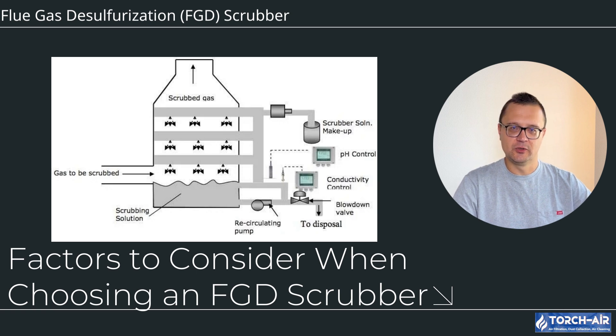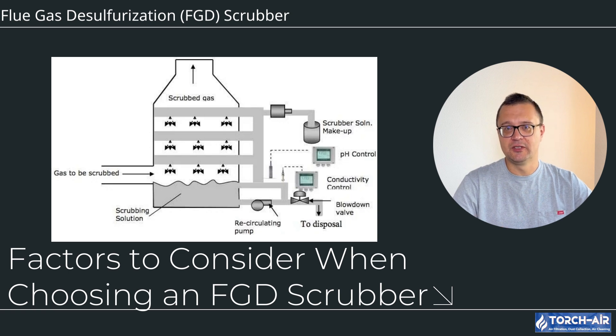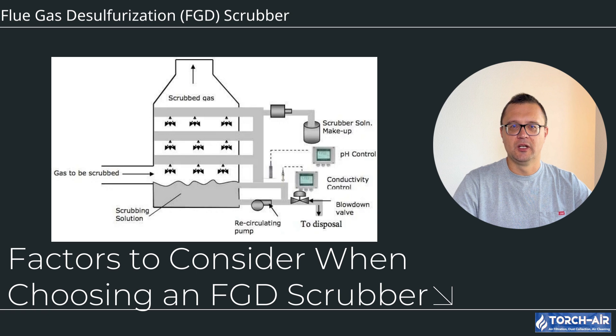Fourth, consider space constraints — wet scrubbers often require more space due to the need for tanks and pumps, whereas dry scrubbers or regenerative systems can be more compact. Fifth, consider by-products management: wet scrubbers produce gypsum, which can be sold or disposed of, while dry scrubbers produce solid waste that may require different handling procedures.